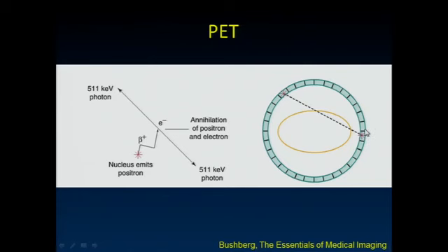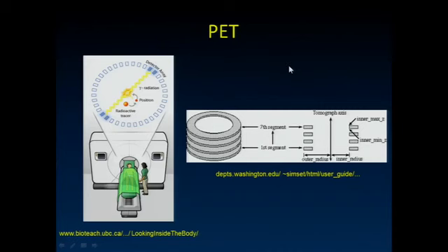And actually that timing is now coming more and more into play in terms of improving the quality of our PET scanners. But realize how difficult that task is. These are traveling at the speed of light. The speed of light is 1 meter per nanosecond. I have to get the timing of those events right down to the level of the 1,000th of a nanosecond if I want to know that event to within a millimeter of accuracy. That's a very challenging problem, but I think we'll see it incorporated in PET CT scanners in the next 5 to 10 years.